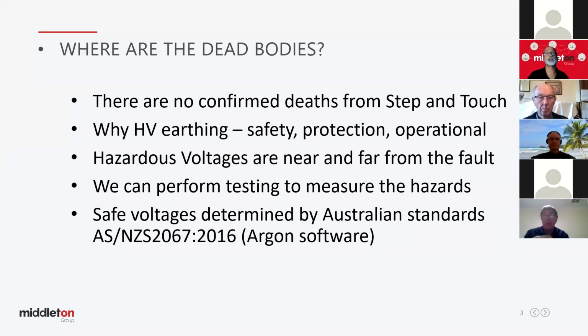Why HV earthing? Well, standards will tell you, if you look into them, that it's there for the safety of people, protection of the equipment, and operational reasons, so that we have a stable grid. We don't want the voltage or the frequency of the grid to be disturbed for all the other customers. So earthing helps us manage that.